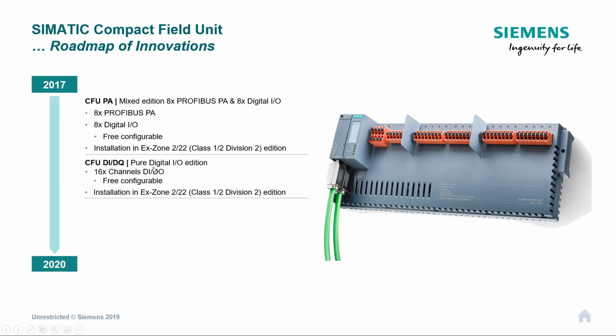Another version came out. If you have a look up here on the Profibus PA, the other nice thing is you've got 8 digital I/O, so input outputs. They're freely configurable. That works nicely. A nice example there might be you might have a little tank farm, so you can have 8 of the Profibus PA radars going in, and if you just want a high-level switch as a backup, then you could bring that into the digital. So you've got some nice features there.